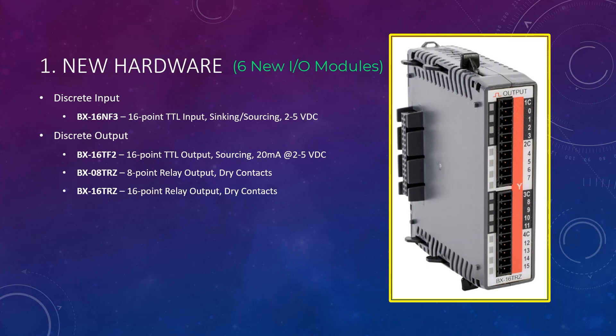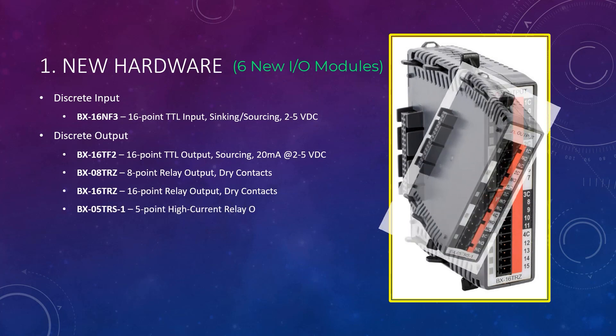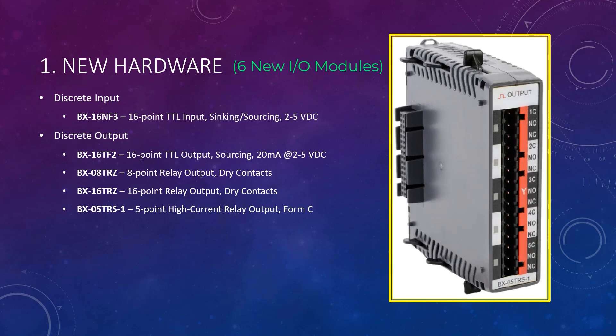This module also comes in a 16-point version called the BX-16TRZ. And finally, in the discrete output category, there is the BX-05TRS-1, which is a 5-point high current relay output module in Form C. The contacts are rated at 8 amps at 12 to 48 volts DC, or 24 to 240 volts AC, or a half amp at 100 to 125 volts DC.